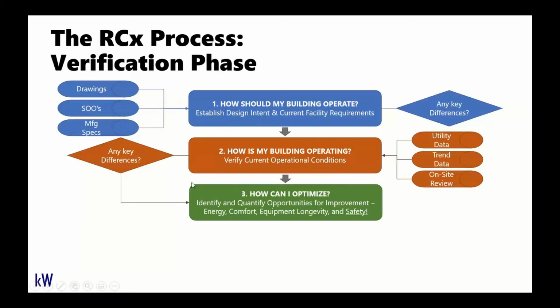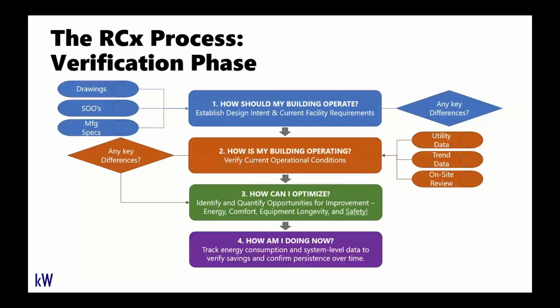So here is again the flowchart of the retro commissioning process that I presented before. And essentially in the verification phase, we are doing the same process. We have now updated the current facility requirements based on what we've seen and investigated from the building. We've attempted to optimize systems to align that, and now we want to look at data to track the energy consumption, track the system level operation to confirm whether or not we've succeeded in aligning the current operations with the design intent or current requirements.